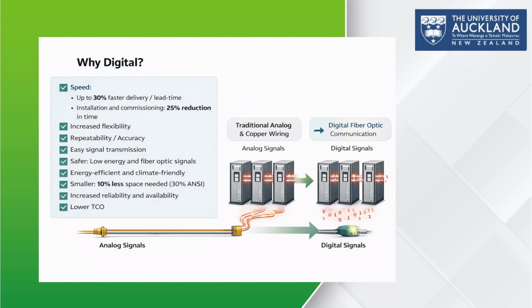Also, digital signals enable easy and efficient transmission without the limitations and noise issues associated with copper wiring. On the safety front, digital systems use very low energy fiber optic signals, which significantly increase safety, especially in a high voltage environment. Also, digital technology requires up to 10% less space, helping optimize substation layouts. So this leads to increased reliability and availability, ensuring better system performance and fewer failures.